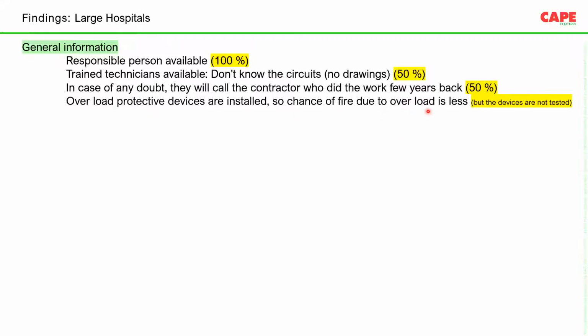Overload protective devices are installed in both cases, especially in medium-level and larger hospitals: ACB, MCCB, MCBs. Technically, since overload protective devices are installed, the chance of a fire due to overload must be negligible, in fact zero, because there is an MCB for a typical load. Let us imagine a 20 amps MCB. The upstream part from the transformer is able to withstand much more than 20 amps, so there is no question. From the MCB to the end circuit downstream, the circuit is able to withstand 20 amps. And if somebody overloads beyond 20 amps, this MCB is supposed to trip. So protective devices are there.